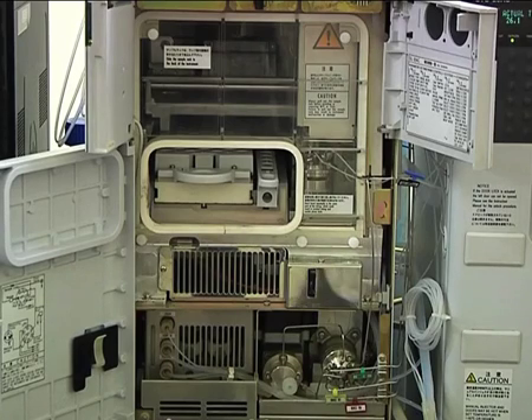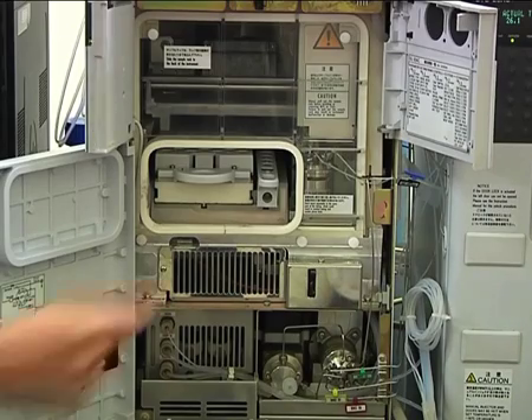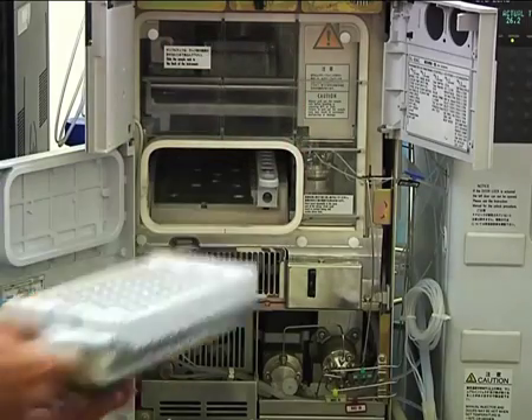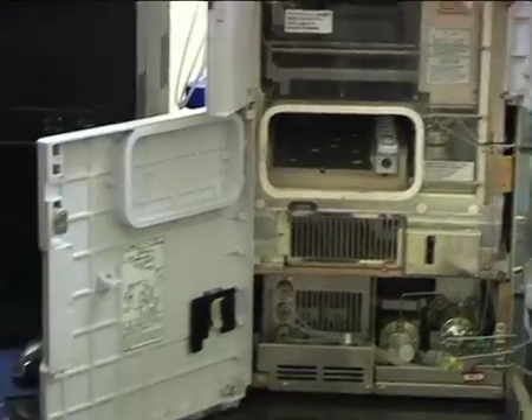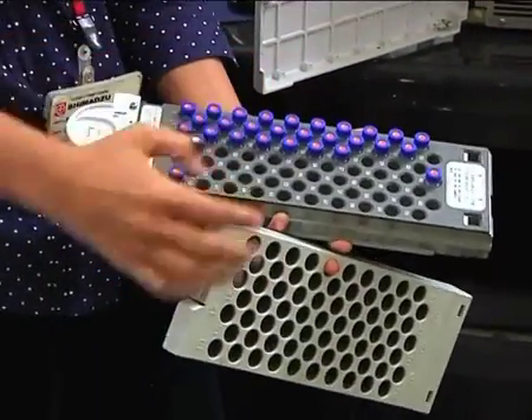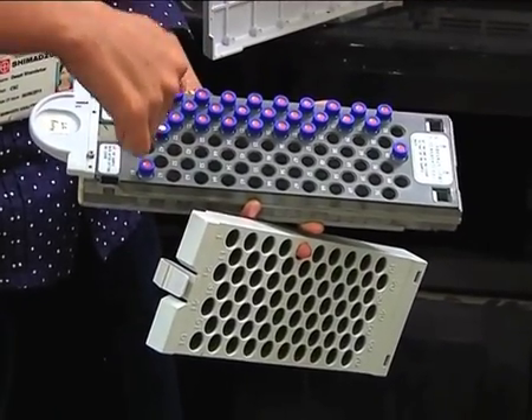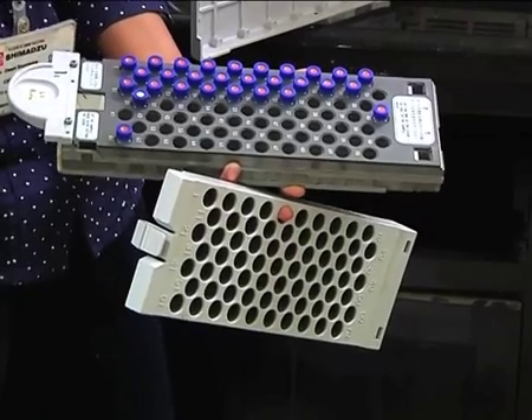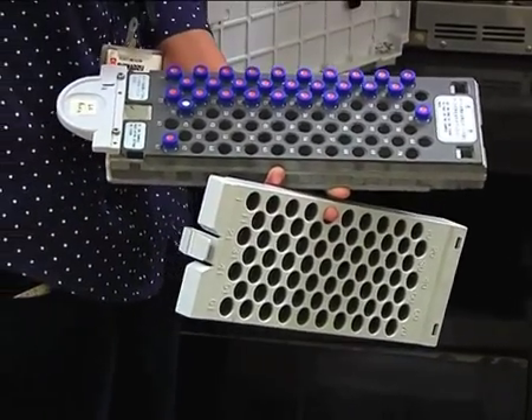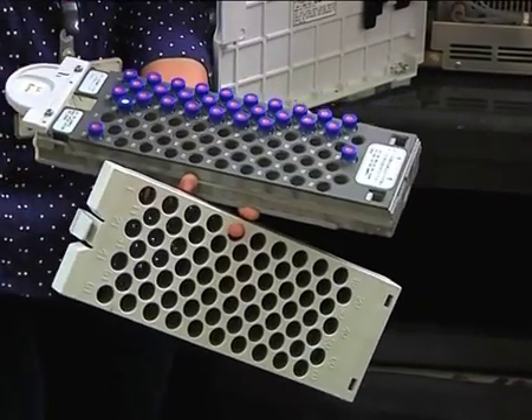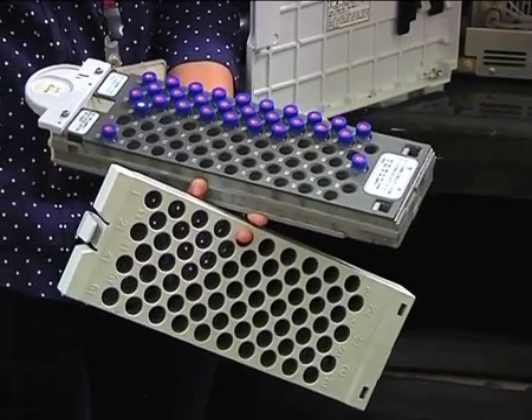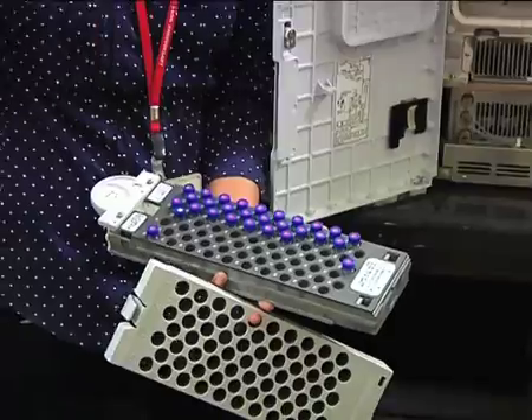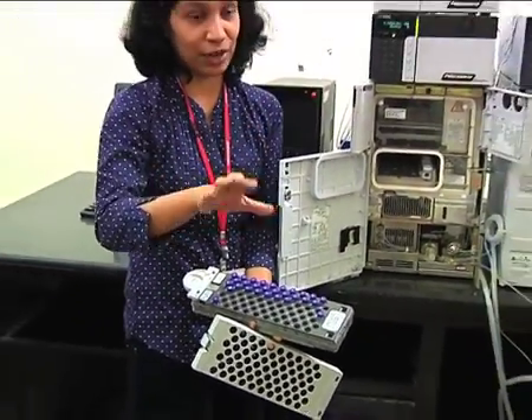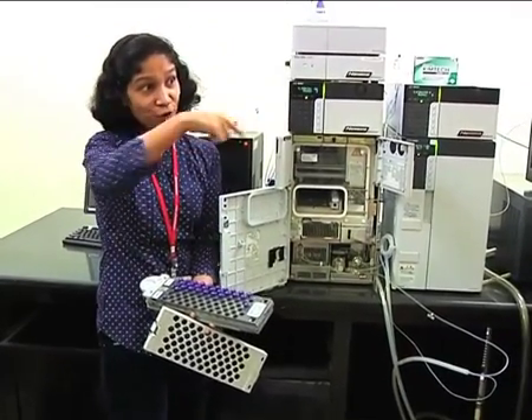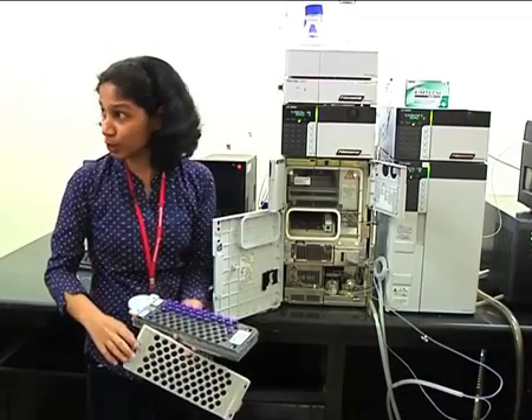So what do you mean by carryover? You have to understand how injection happens. There is a needle. You will put your samples in auto sampler vials like this. You fill the vial, and the needle will come, pierce through the vial and take the sample. So the outer surface of the needle comes in contact with the sample. Now when the needle goes to the injection port and injects the sample, there is a possibility that whatever is stuck to its outer surface will get deposited on the injector port. When you perform the next analysis, even if you are not injecting sample, and are injecting only organic solvent or only water, traces of those residues will pass and give you a response. That is called carryover.